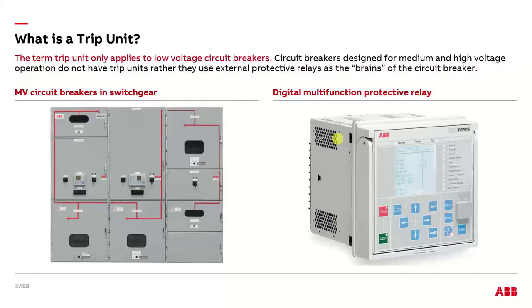So we build switchgear at ABB, medium voltage vacuum switchgear, and we'll install Schweitzer relays or Multilin relays. We obviously have our own line of relays that are good, but a lot of customers specify, because of their install base, they might be a Schweitzer user or an ABB user, so they want that relay, but they want ABB's breaker. So it's mix and match. And that's the big difference between the trip unit in the low voltage breakers versus the medium and high voltage, what they're called a circuit breaker.